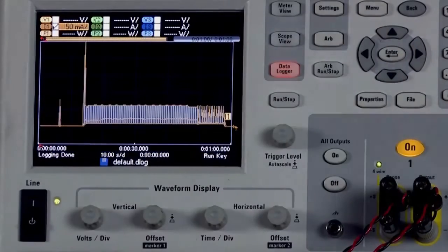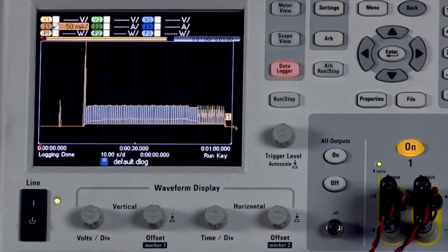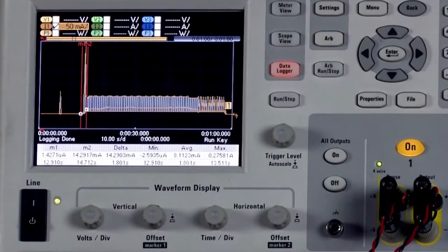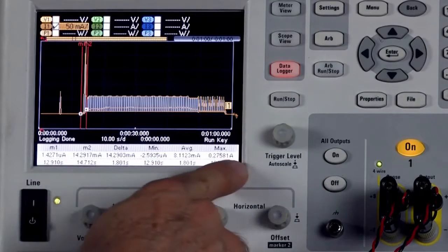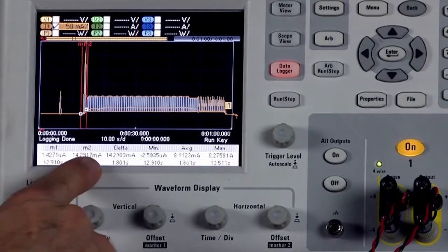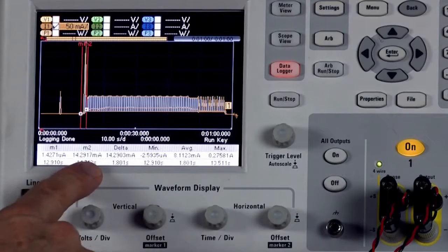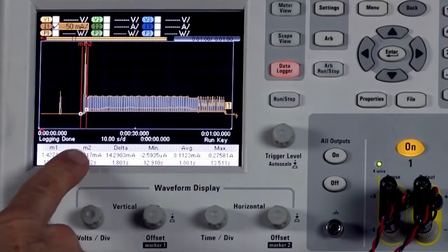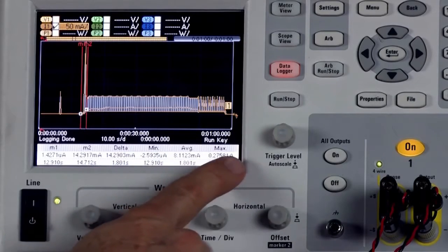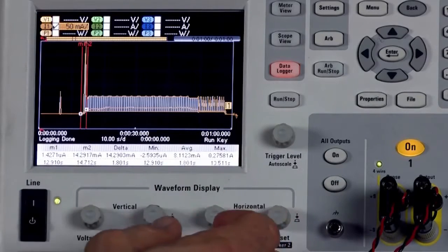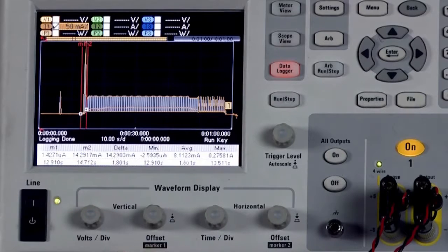So we'll close that. And now let's move on to step 5, where we analyze our data log record. All I need to do is hit the data logger button again, and you can see 2 markers appear. These markers are used to help you analyze the waveform that you're looking at. If you look at the text at the bottom of the display, you can see M1 for marker 1 and M2 for marker 2 tell you what is the current at that place in the time scale. The delta tells you the difference between marker 1 and marker 2. And finally, the min, the average, and the max tells you in between those 2 markers what are the minimum, average, and maximum values. So we're going to use these to analyze the data.